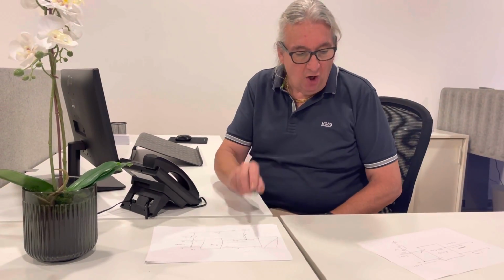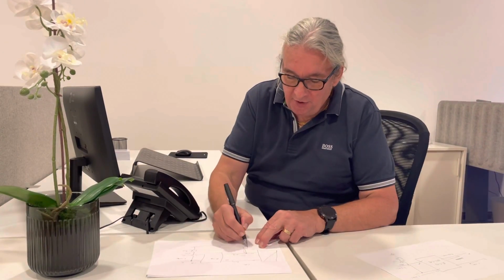This bonding can't stay permanently here, because if this stays permanently here, what I spoke about is the upstream RCD will trip. That's why we have to do this as a temporary, and we put this as a relay. And we can only close this relay when the inverter is in islanding mode. It's not connected to the AC. It might be connected to the AC, but still operating in islanding mode. Once that connection makes to the AC and those internal relays close in the inverter, then this bond must be removed. Otherwise, it will trip the upstream RCD.